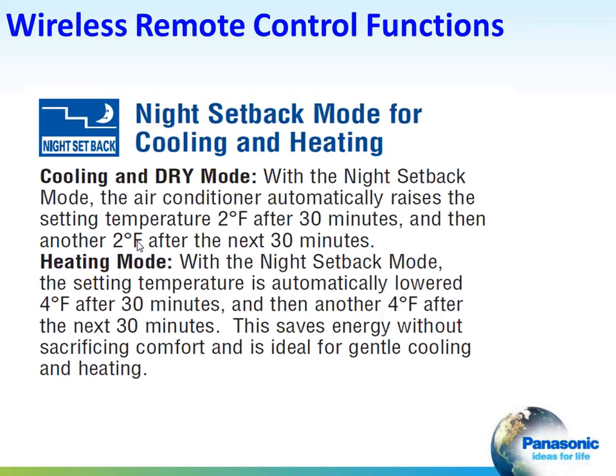There's also night setback features, so the customer doesn't have to think about it. In the cooling and dry mode, the night setback will raise the temperature 2 degrees after 30 minutes and then another 2 degrees after the next 30 minutes. In the heating mode, the setting temperature is automatically lowered 4 degrees after 30 minutes and then another 4 degrees in the next 30 minutes. This saves energy without having to program in night setback temperatures and set points.